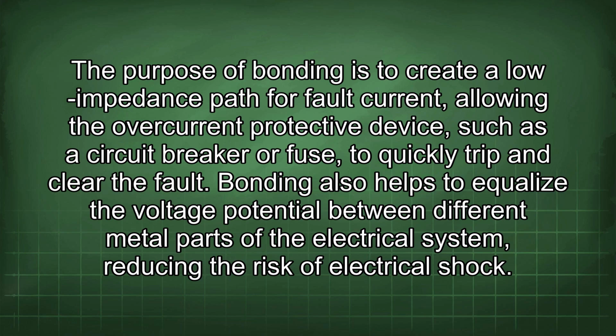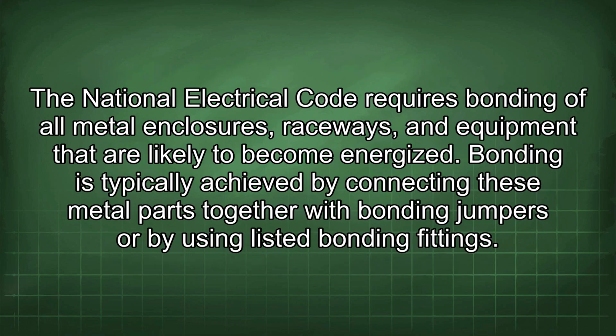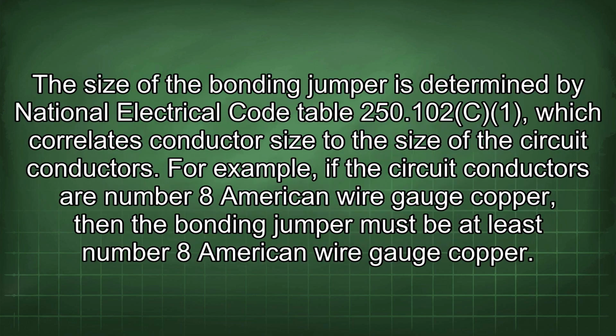The National Electrical Code requires bonding of all metal enclosures, raceways, and equipment that are likely to become energized. Bonding is typically achieved by connecting these metal parts together with bonding jumpers or by using listed bonding fittings. The size of the bonding jumper is determined by National Electrical Code Table 250.102, which correlates conductor size to the size of the circuit conductors.